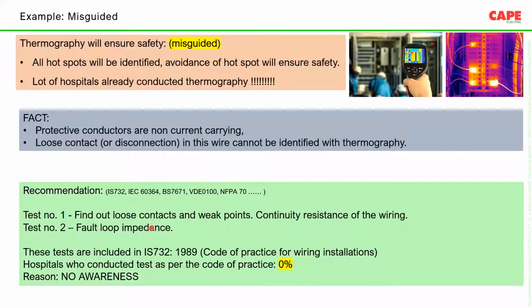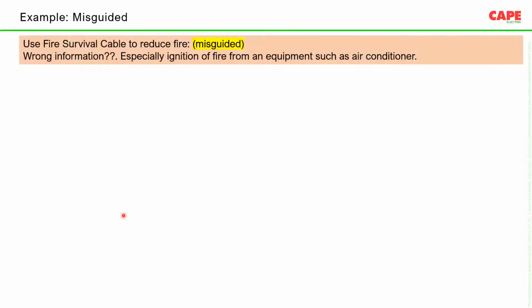Imagine you have an existing installation. You want to find out whether the installation wires have degraded or some loose contacts have occurred in the wire and so on. With the second test, fault loop impedance, you will be able to find out. So there are advanced tests recommended in the standard, which are actually mandatory as per the code of practice, which we don't do. Whereas we go for thermography. I would say this is misguided information. The second misguided idea: if we ask about fire survival, people always think it is a subject related to wire. Then they immediately jump out and say, yeah, I know, it's a wire.